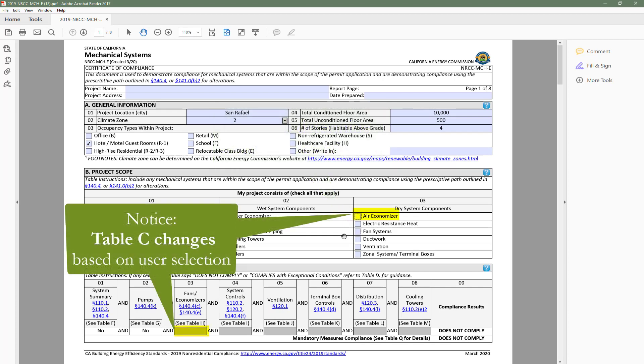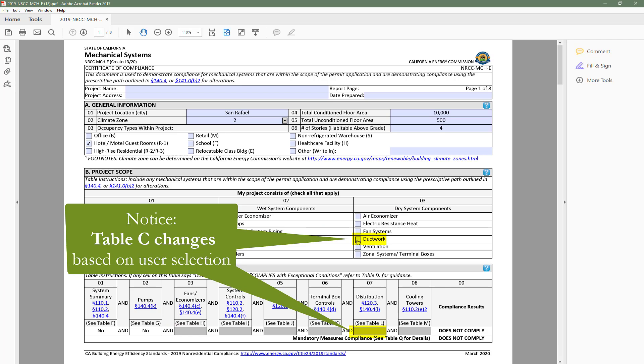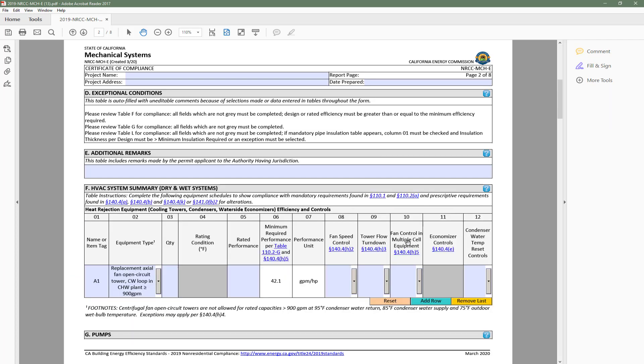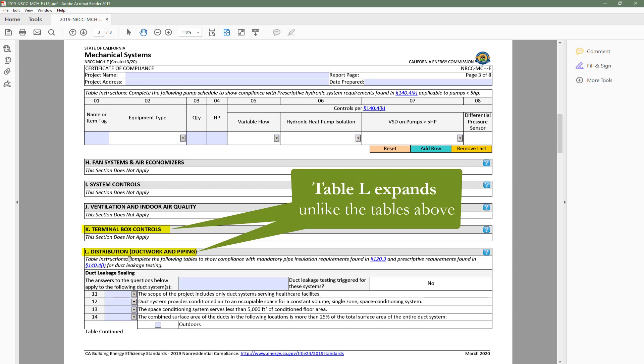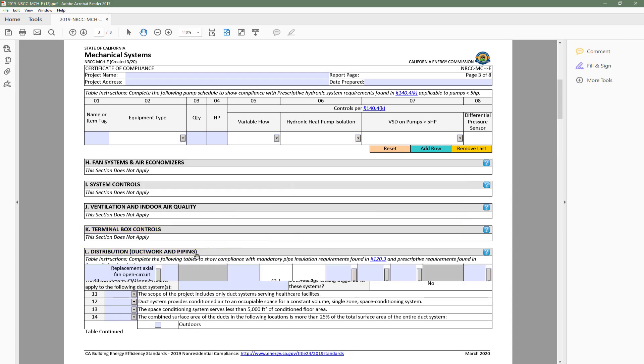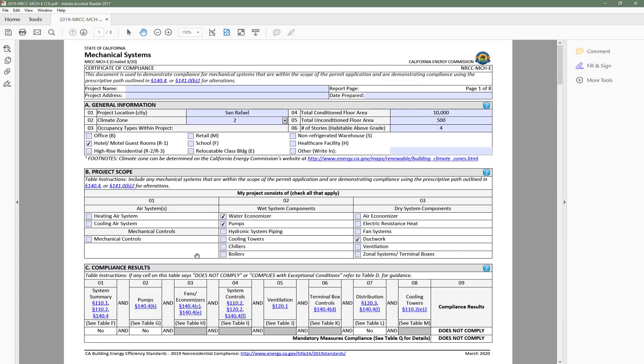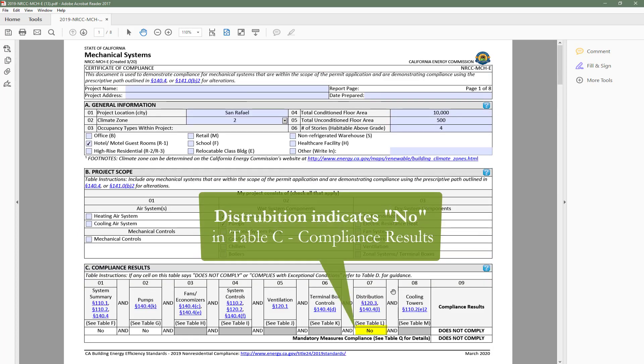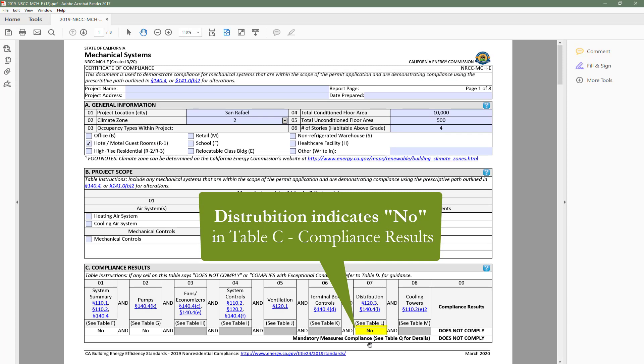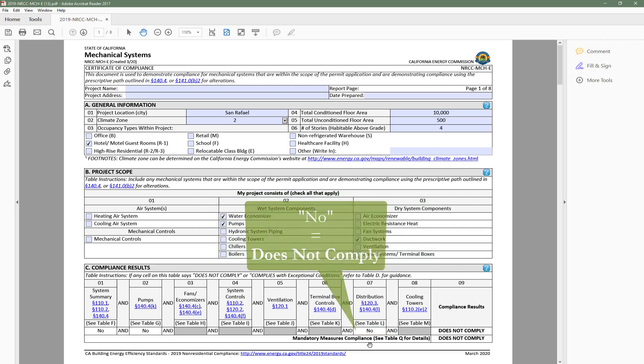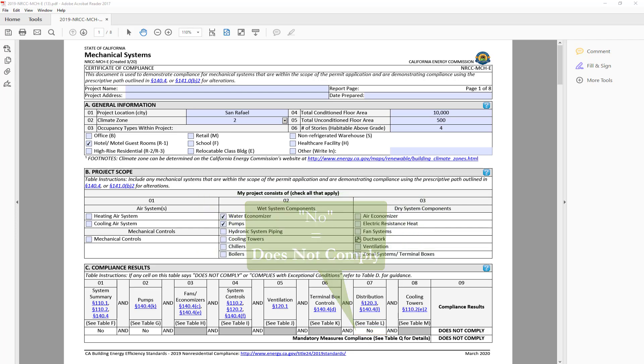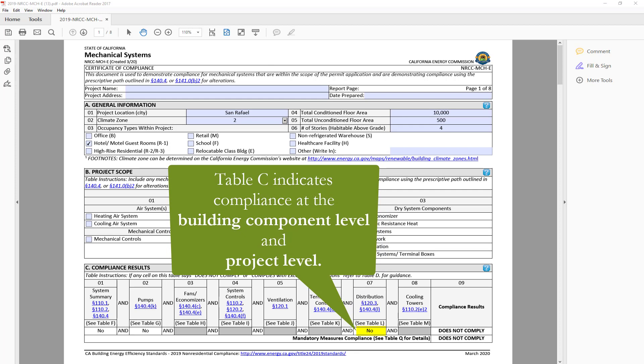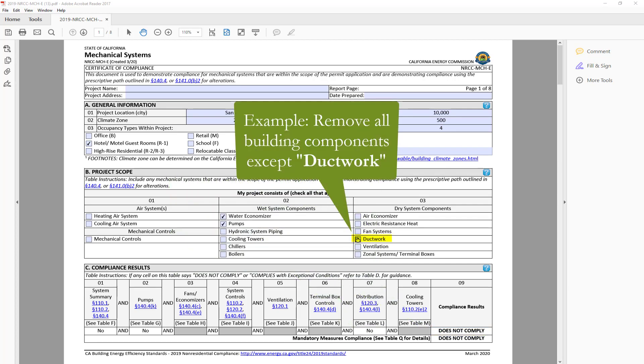This table is important because it decides which tables to trigger throughout the form. For example, if our project is adding or altering a duct system, we would select Duct Work in Table B and Table L distribution would expand. You'll also notice that the distribution column in Table C compliance results has updated itself and indicates no. This is another great feature of the dynamic forms, which is the ability to indicate compliance at the building component level as well as at the project level.